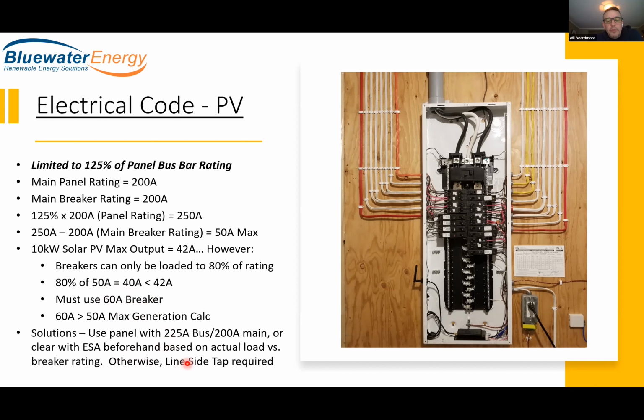Or we have to do what's called a line side tap. So we're using insulation piercing connectors, and we're crimping onto these here or at the meter base. That requires isolation from the utility, so we have to bring in the utility, they have to disconnect the home at the transformer on the road, and then we can install the solar. So it's a little bit of extra work if that's what we're doing. If you don't have a 225 amp rated panel, that's the only way to proceed on a 10 kilowatt installation.